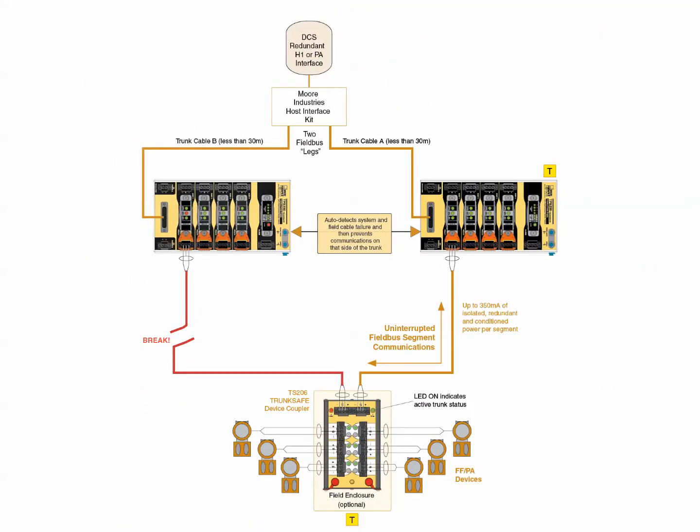Simultaneously, the power conditioner, which continuously monitors the segment cable legs, also immediately detects, reports, and deactivates its terminator and isolates the faulty leg.